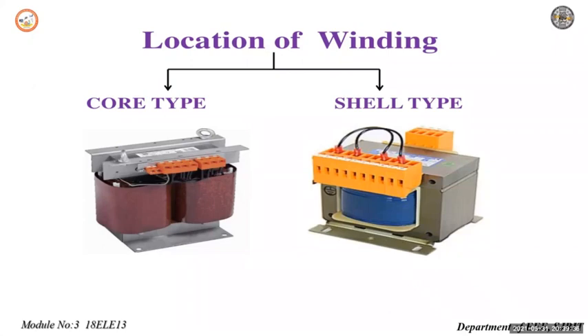In the figure, you can see the schematic representation of the core type transformer. Figure B shows the shell type. The coils used here are cylindrical type, wound in helical layers, with different layers insulated from each other by paper or mica. Both the coils are placed on both the limbs. The low voltage coil is placed inside, near the core, while the high voltage coil surrounds the low voltage coil.